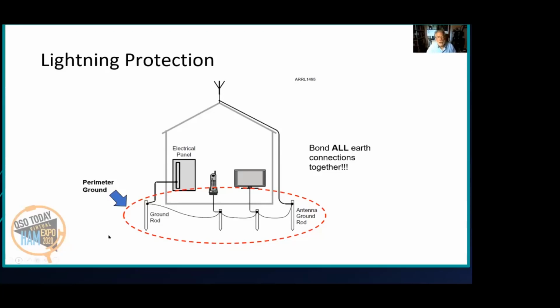So that can be very hazardous and destructive. So outside the house, you bond all your ground rods together with heavy wire, number 6, number 8, number 2, whatever you got, whatever your code says, and you use properly rated clamps if you're going to bury them. You can use welded connections with one-shots or CAD welds, and those are kind of fun to use, and you create a great perimeter ground.